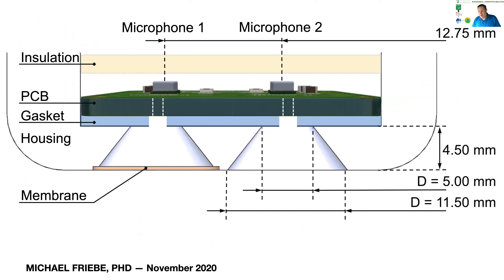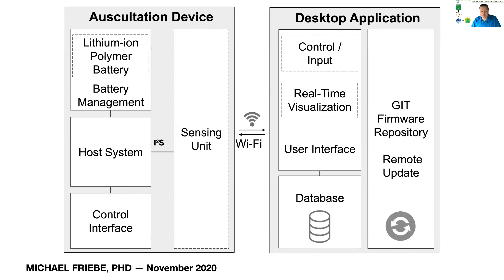In the meantime, we have improved the system significantly. We're now using two microphones — membrane microphones or non-membrane microphones. It's almost a stereo approach, but not used in that sense. These microphones now also allow us to get rid of the ambient noise and just focus on the auscultation sounds that are directly coming from the carotids.